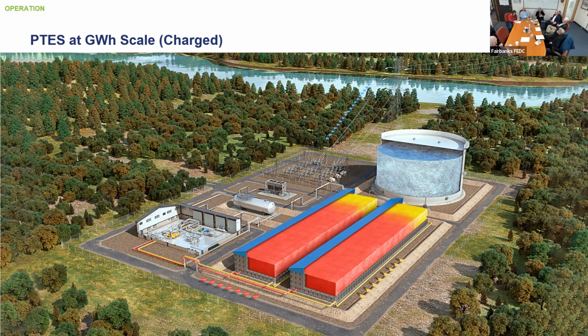Much like if you pump up a bike pump and accidentally grab down at the bottom, you burn yourself - it's the same basic process. So you increase the temperature and pressure of the fluid. Then we have heat exchangers, some of the boxes in that turbine hall, that transfer that heat from the CO2 into the heat transfer fluid before it goes into the concrete. So it's that process of heat transfer that accomplishes the reduction in temperature and fluid density at the same time. We do the same process on the low pressure side.